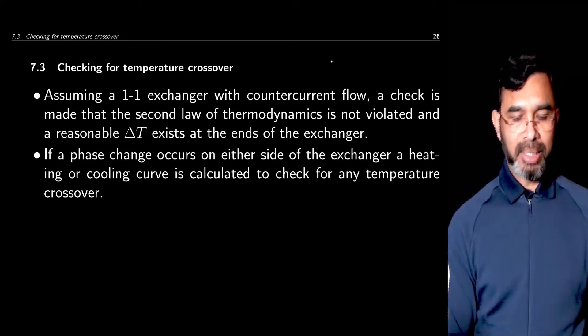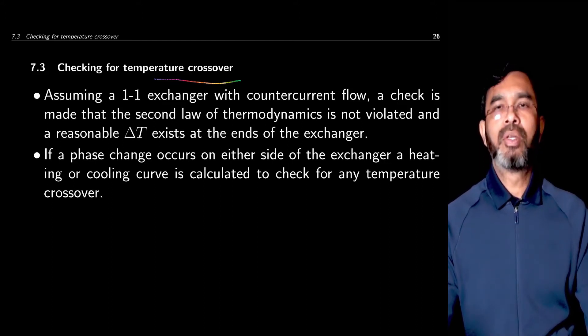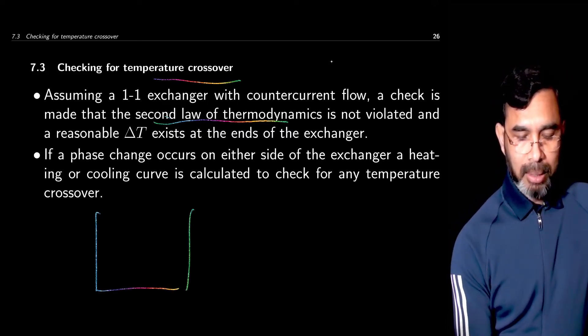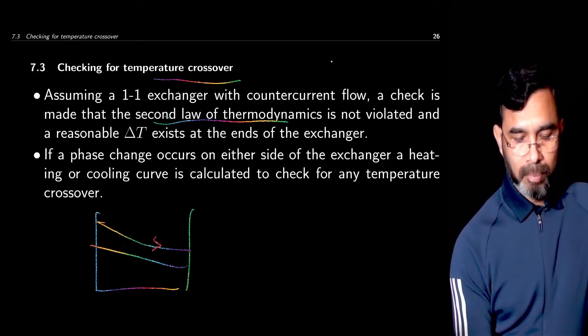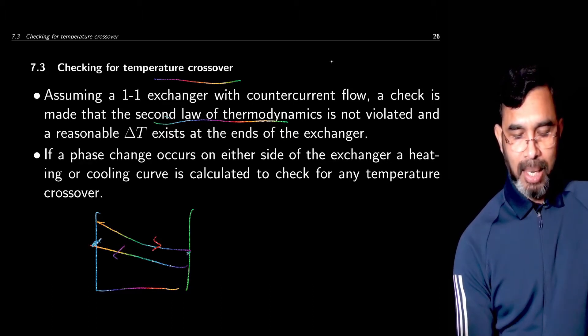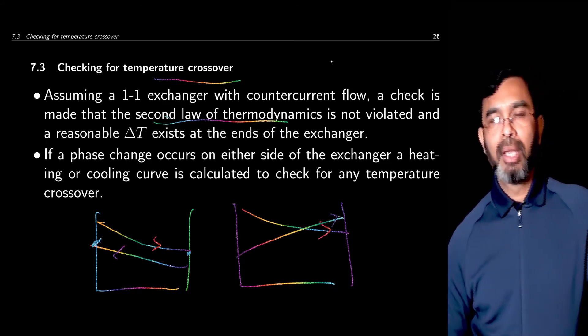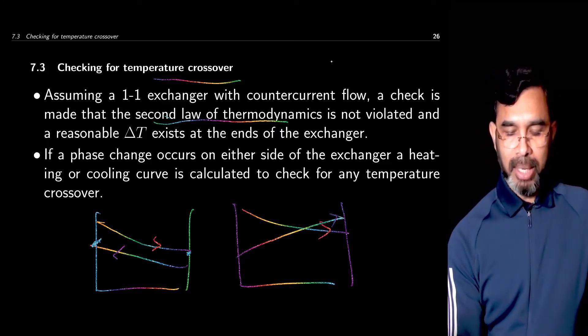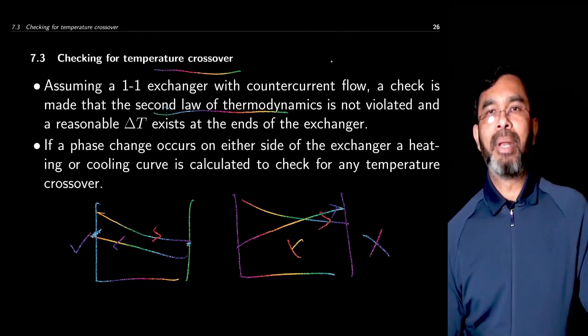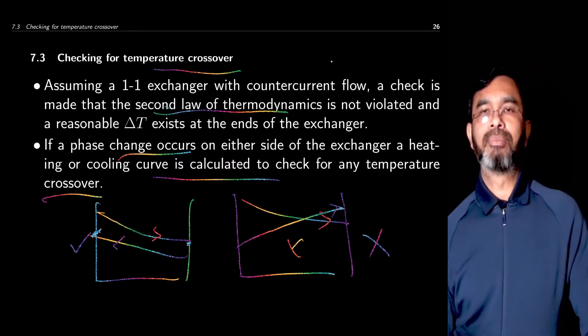When you have done the energy balance, you need to check whether there is a temperature crossover. This might happen with parallel flow or counter-current flow. You must always maintain that the second law of thermodynamics is not violated. For a counter-current heat exchanger, it is possible for the exit temperature of the cold stream to be higher than the exit temperature of the hot stream. However, that temperature condition is not possible for parallel flow. So you need to make sure this scenario is not happening with the temperature range under consideration, especially when a phase change is occurring.